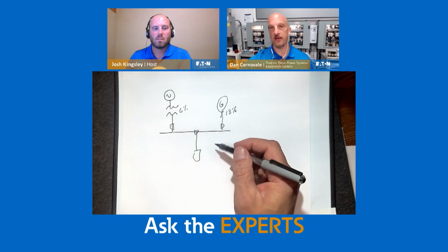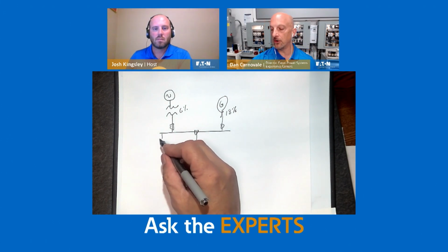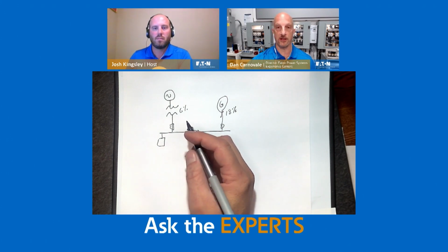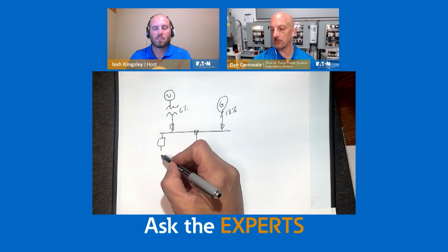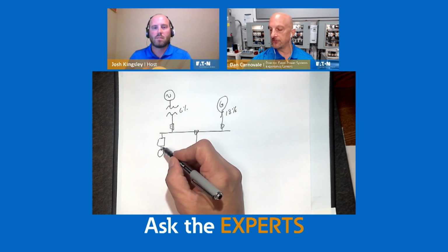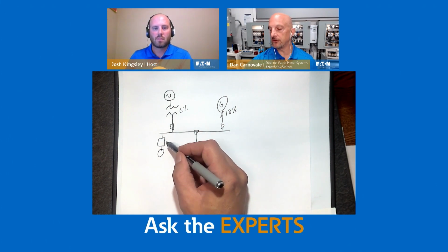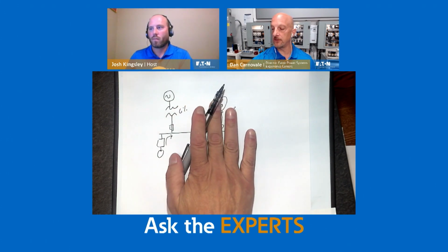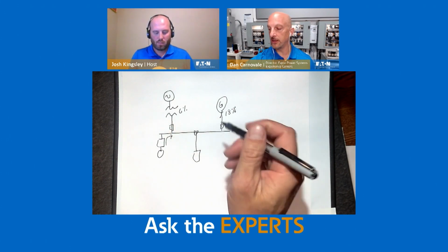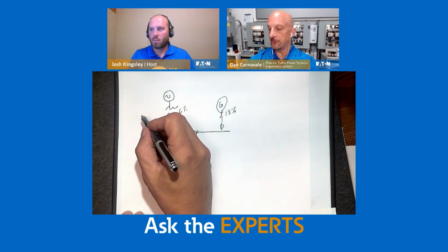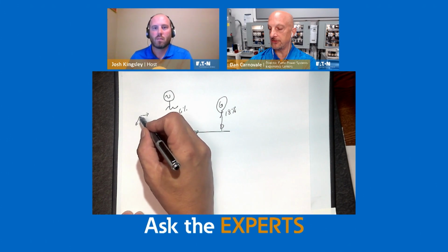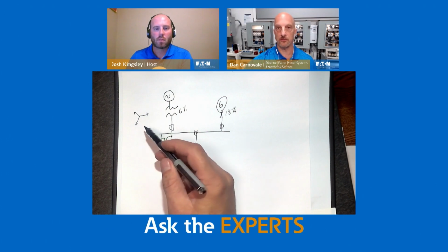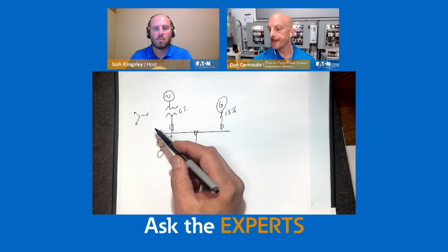So if you had no generator, but you added one later and you had a whole bunch of harmonic producing loads. And again, we're going to call harmonic producing loads kind of the new normal, anything electronic, but specific to today, we're talking about drives. You have all these VFDs or other things that are adding harmonics to the system, and they want to flow back to the path of least impedance. If the generator is offline, that current's going to flow back up to the source. And by the way, it's going to flow out, say, for example, on A and then back on B and C. A lot of people think harmonics flow to ground, but they don't. They flow out on the phase conductors and back on the other phases or the neutral.